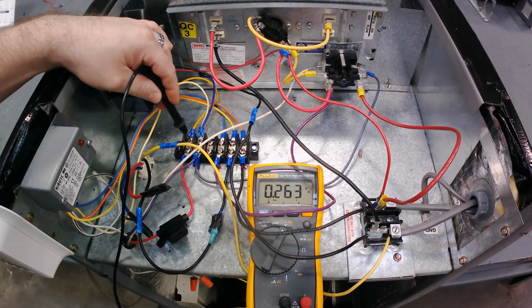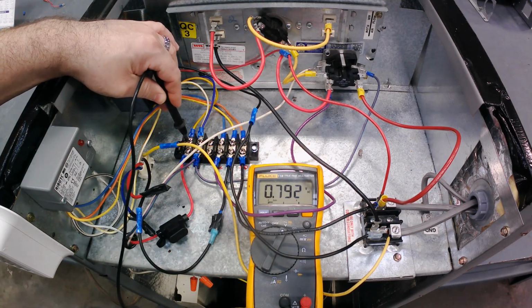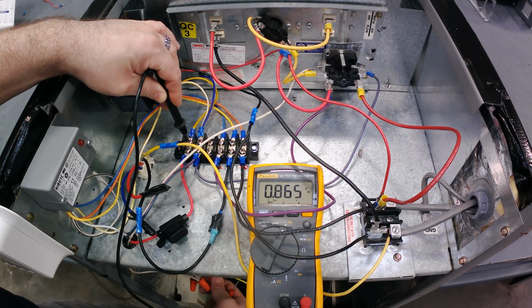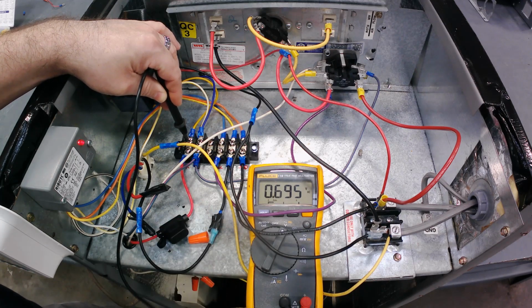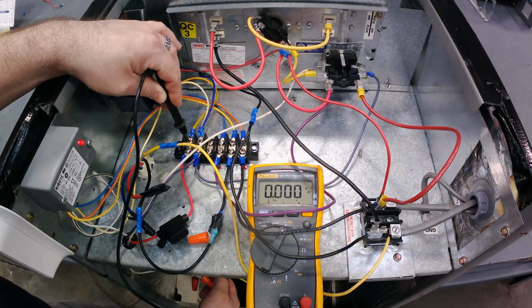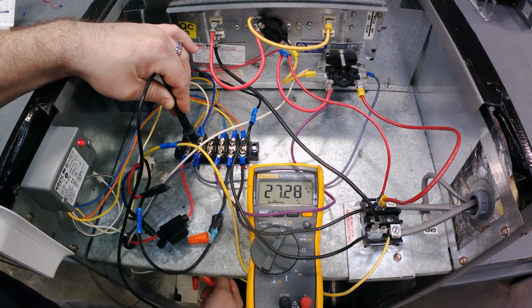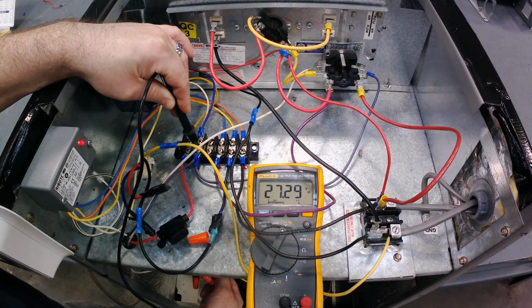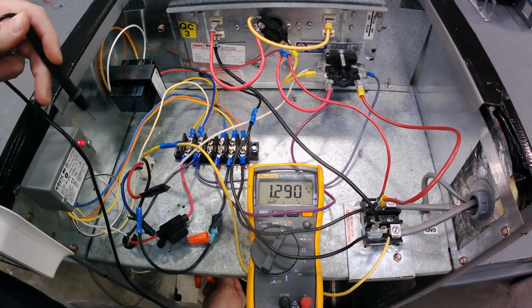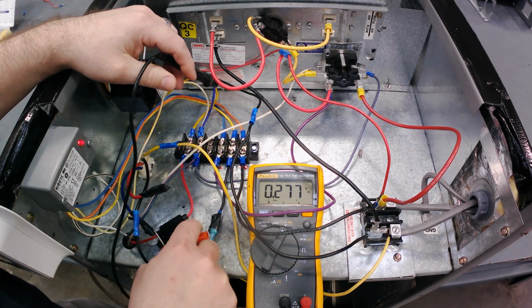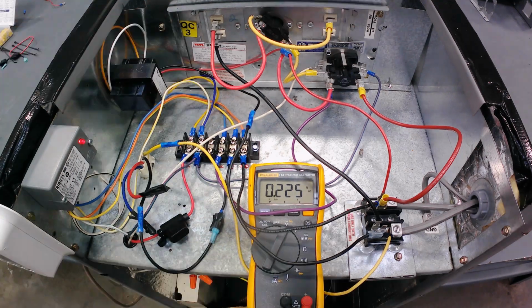If we wanted to check the voltage to the coil, I would need to go down to the low voltage that we wired. Take that thermostat or that cap off. And I've got 27 volts on my rib relay coil, and you can see over here that that little LED, that red LED light is on.